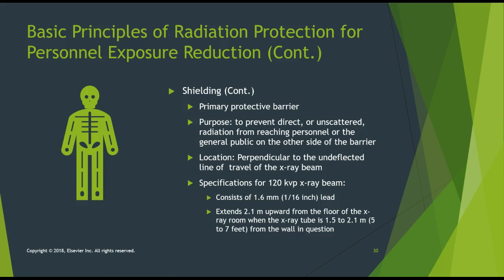The specifications are for a 120 kVp X-ray beam, the highest kVp that the tube is capable of. That's what the barrier has to be designed to prevent from going through. So for a 120 kVp X-ray beam, that wall needs to have 1.6 millimeters of lead in it. It has to extend 2.1 meters from the floor of the X-ray room when the X-ray tube is 1.5 to 2.1 meters from the wall in question. So all of these distances and measurements are taken into account when they build imaging suites.